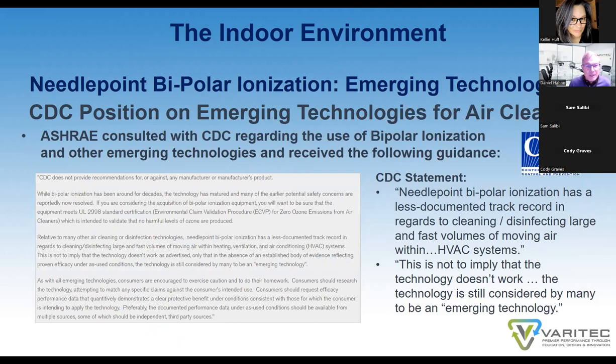The CDC has acknowledged bipolar ionization as an emerging technology. It does make the statement regarding some ion generators are ozone generators. Needlepoint bipolar ionization is not an ozone generator and conforms to UL standard 2998 as a non-ozone generator. So because you use ionization does not mean that you're going to have added levels of ozone in the building, depending on which type of generator is used for the design.